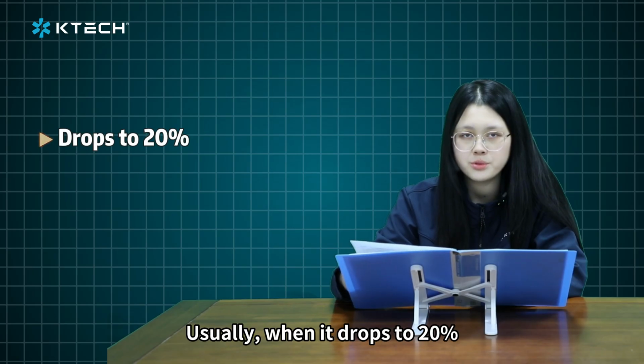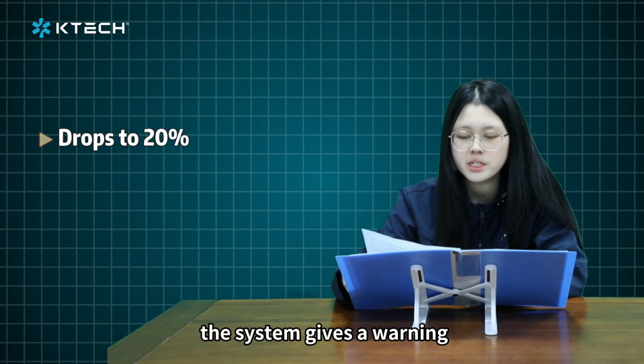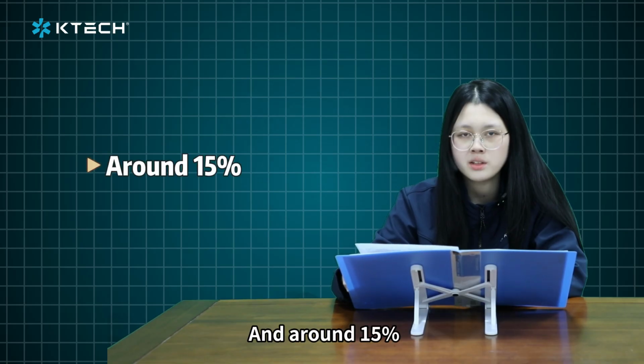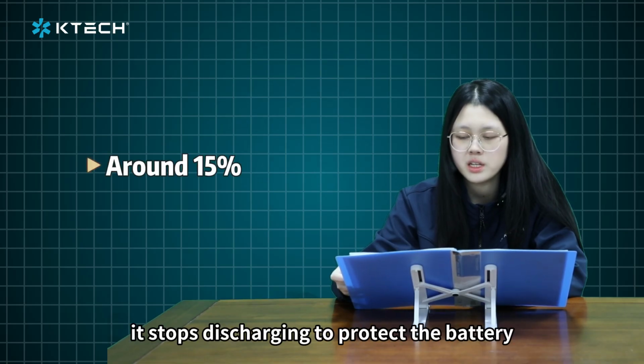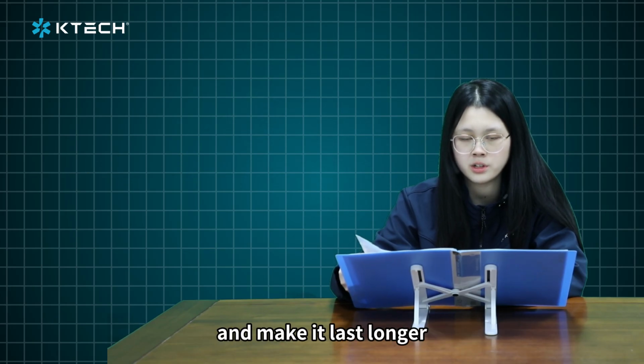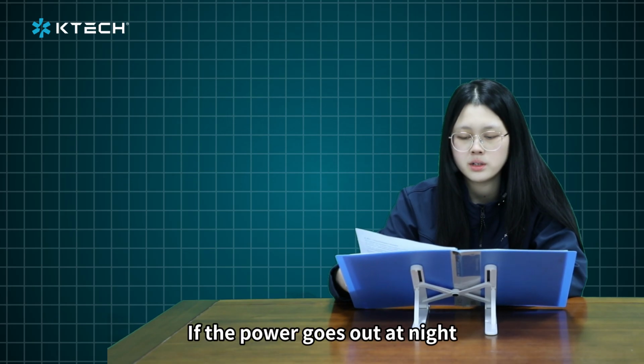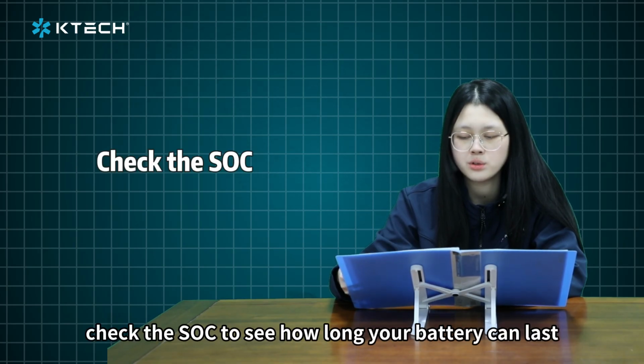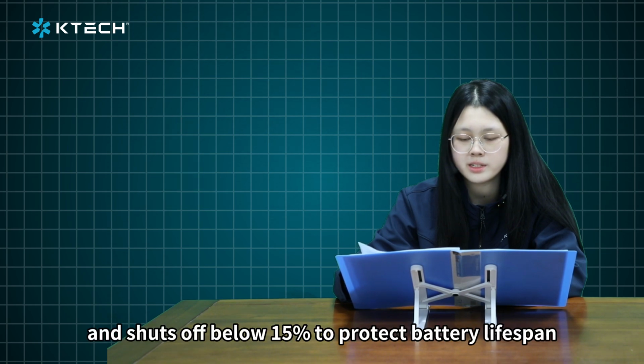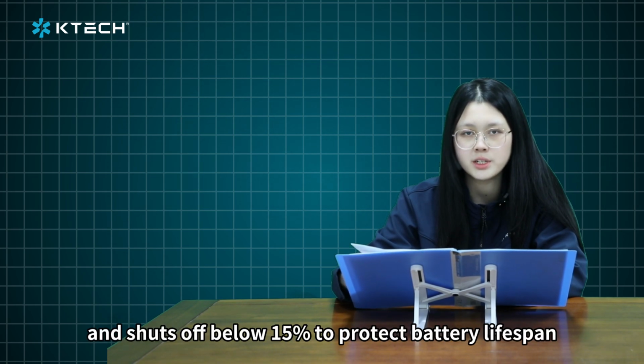Usually, when it drops to 20%, the system gives a warning, and around 15%, it stops discharging to protect the battery and make it last longer. If the power goes out at night, check the SOC to see how long your battery can last. It reminds you below 20% and shuts off below 15% to protect battery lifespan.